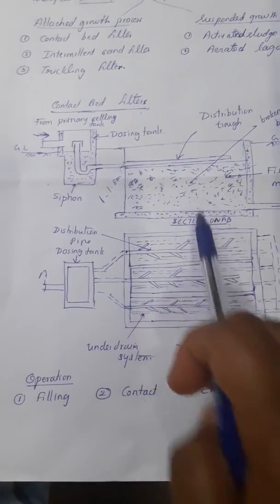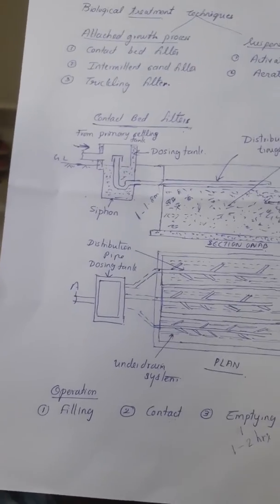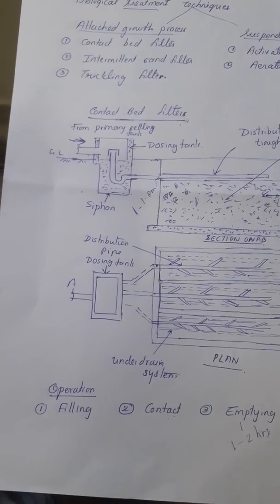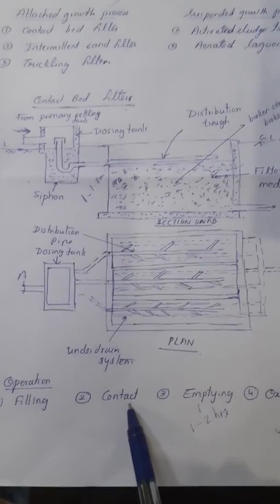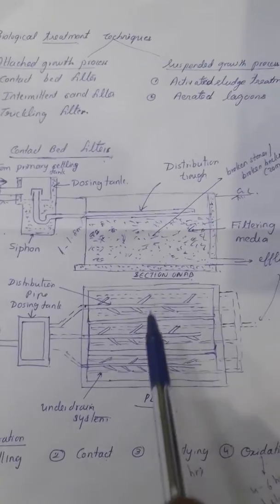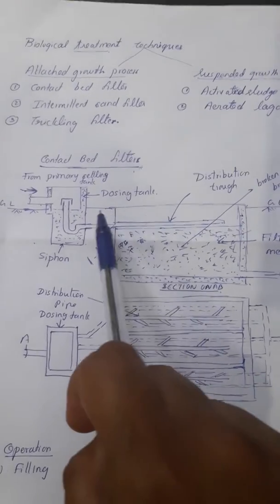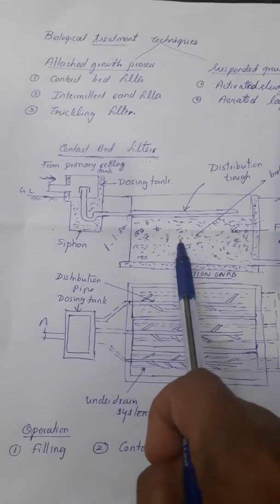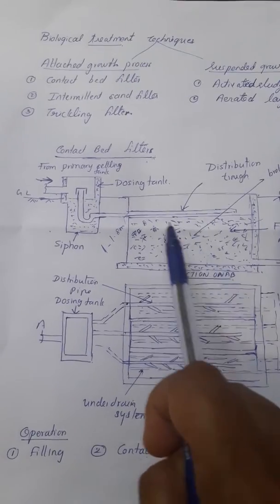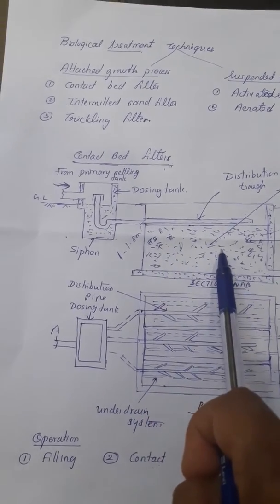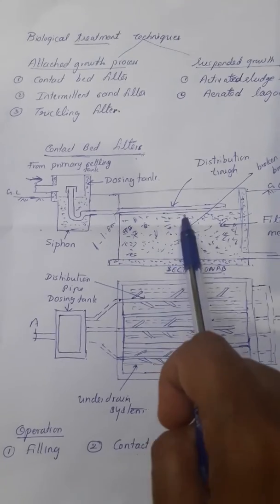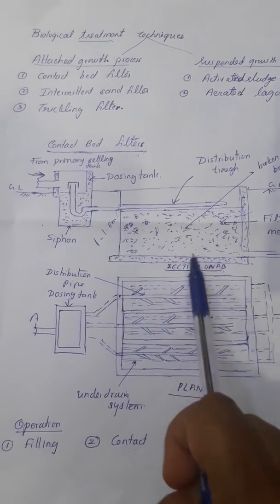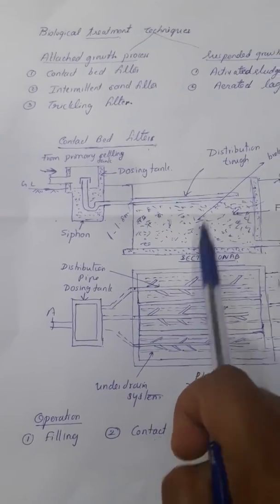The second operation is contact. Contact means the dosing tank outlet is then closed, and the sewage admitted over the contact bed is allowed to stand for about 2 hours. During this period, the colloid and dissolved matter get transferred to the filter media and come in contact with the bacterial film covering the filter media.